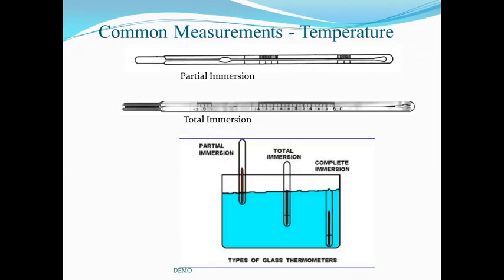Complete immersion types are immersed to cover the entire glass. If the thermometer needs to be removed from the liquid, it must be read quickly to reduce heat loss during the reading.